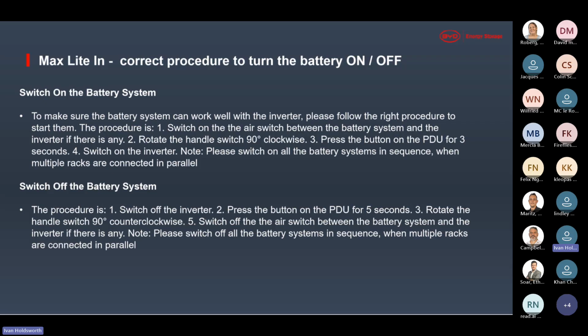And for your turn off procedure, you want to make sure your inverter is off, and then you hold the button on the PDU for 5 seconds to turn the battery off, and then you can rotate the handle. Only when everything's off, and you wait, say, 2 or 5 minutes, wait 5 minutes for safety, can you open all your fuses if need be. It's important to only open any fuses when everything's off.